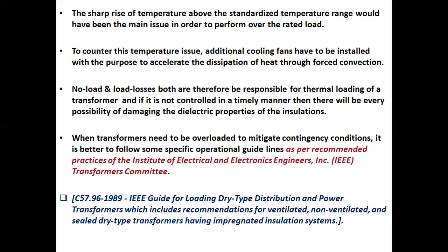properties of the insulation. When transformers need to be overloaded to mitigate contingency conditions, it is better to follow specific operational guidelines as per the recommended practices of the Institute of Electrical and Electronics Engineers, the IEEE Transformer Committee.